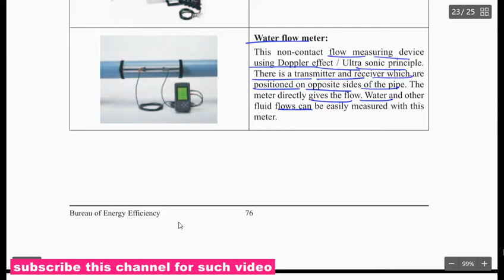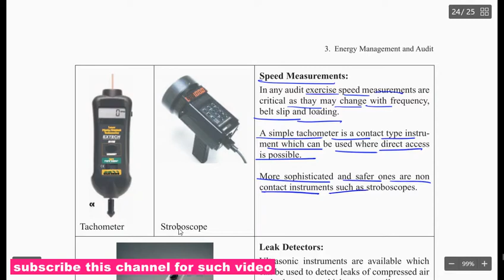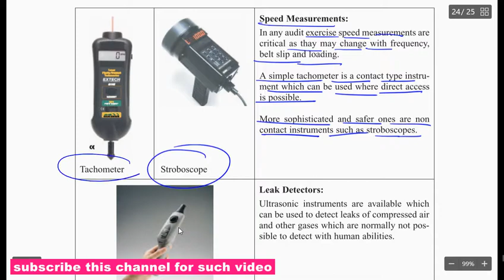Then speed measurement. In any audit exercise, speed measurements are critical as they may change with frequency, belt slip and loading. A simple tachometer is a contact type instrument which can be used where direct access is possible. More sophisticated and safer ones are non-contact instruments such as stroboscopes. That is called a stroboscope, and this is called a tachometer.